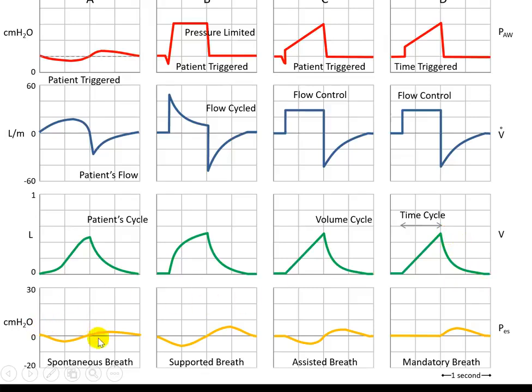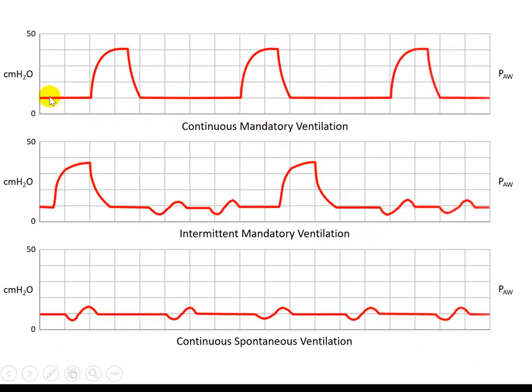We appreciate that there are only four different types of breaths in any mode: spontaneous, supported, assisted, or mandatory. Putting this together gives us the breath sequences. In continuous mandatory ventilation, all breaths are time triggered, the machine delivers the control — either volume or pressure — and the cycle is either time or volume. This is continuous mandatory ventilation.